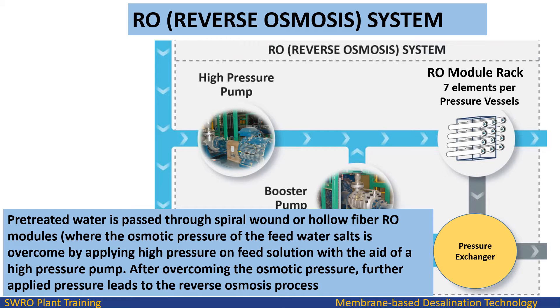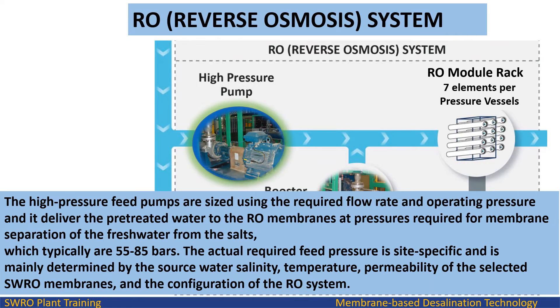Pre-treated water is passed through spiral wound or hollow fiber RO modules, where the osmotic pressure of the feed water salts is overcome by applying high pressure on the feed solution with the aid of a high pressure pump. After overcoming the osmotic pressure, further applied pressure leads to the reverse osmosis process. The high pressure feed pumps are sized using the required flow rate and operating pressure, and deliver the pre-treated water to the RO membranes at pressures required for membrane separation of fresh water from the salts.